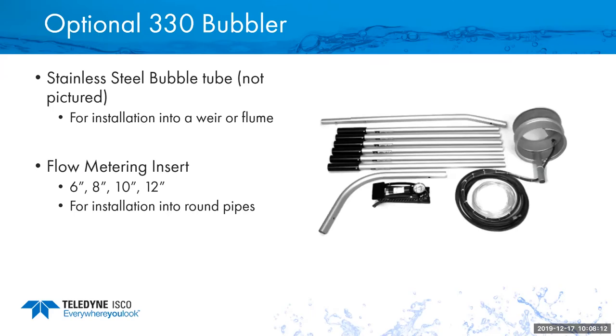One of the options, instead of it needing a primary device, a weir or a flume, you can purchase what are called flow metering inserts. A flow metering insert is a way of making a round pipe into a weir. So what it does is it creates a dam-like structure in the flow, and you use the bubbler to measure the level of the water behind the flow metering insert. Great for round pipe installations instead of having to install a weir or a flume.